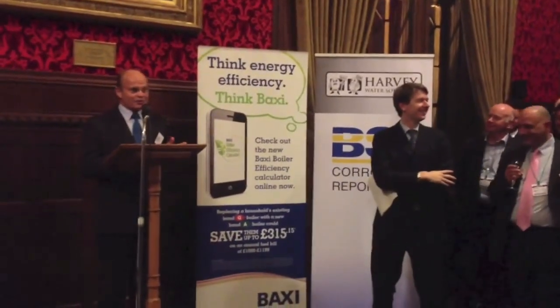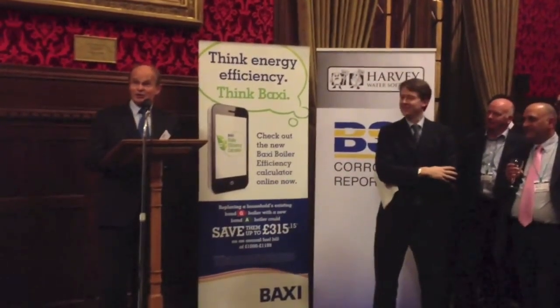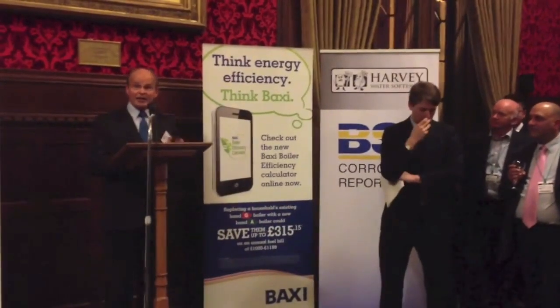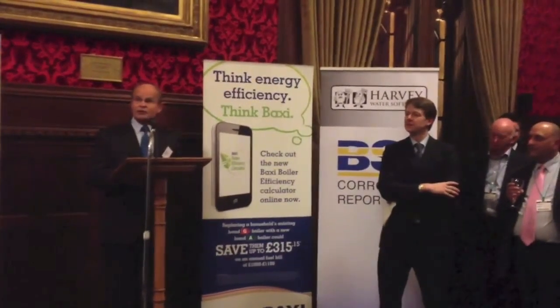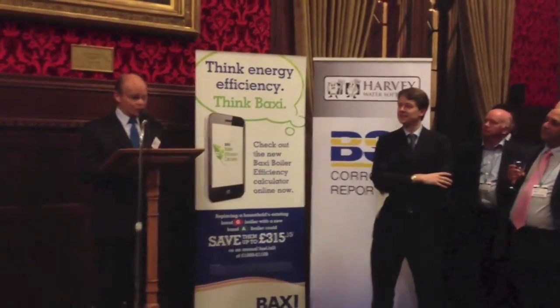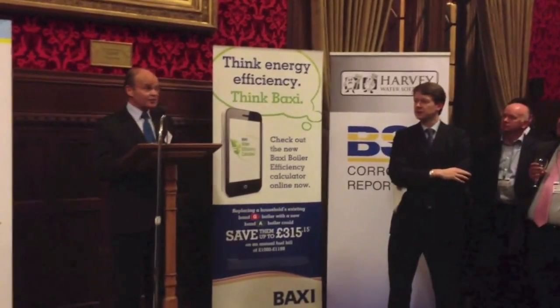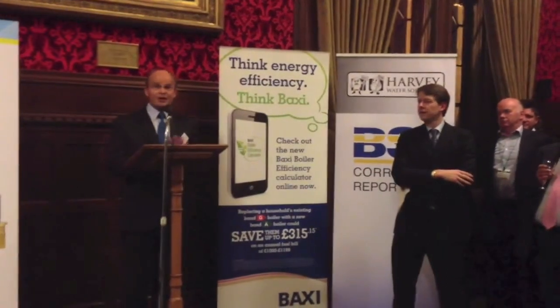The first domestic water softener was installed in 1916 and for the first 70 years there was never a question about corrosion, because there wasn't any. But during the 1980s, the introduction of condensing boilers introduced aluminium, and they had an awful lot of problems with corrosion. The reason for that is that the corrosion inhibitors at that time were designed for cast iron, and when mixed with softened water it caused all sorts of problems. So in 1992 they introduced a British standard for water treatment for central heating systems and essentially said you can't use softened water — and that's the myth that was born.